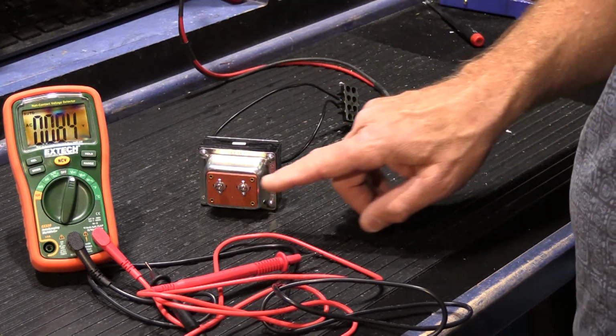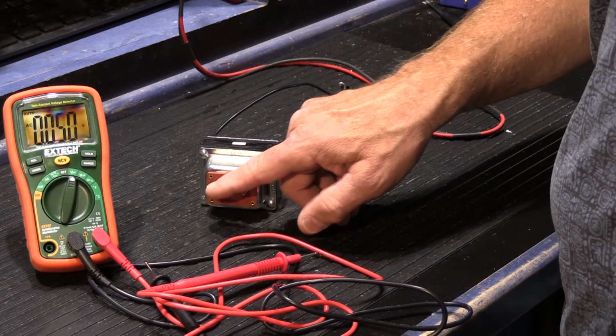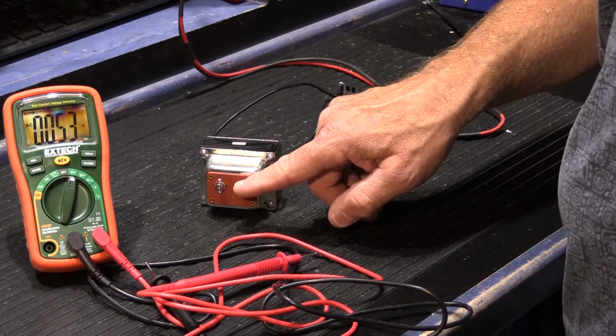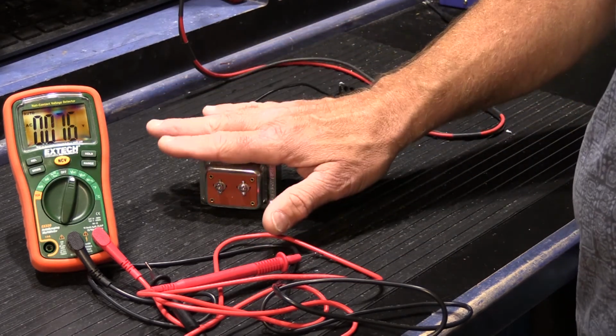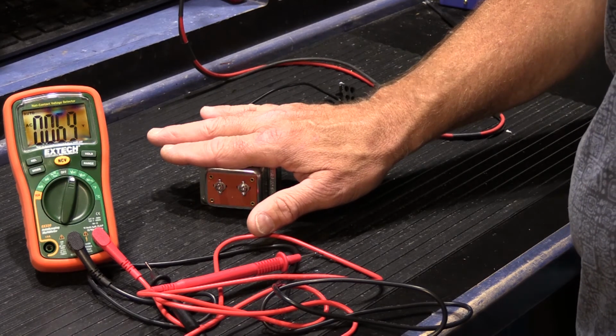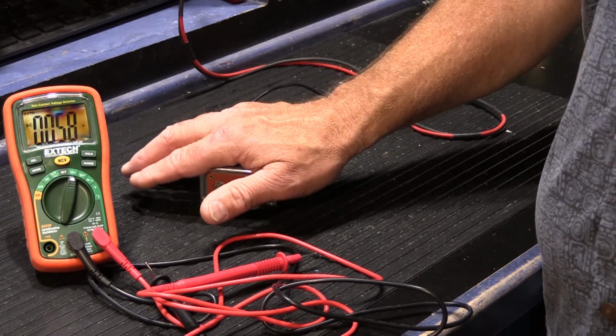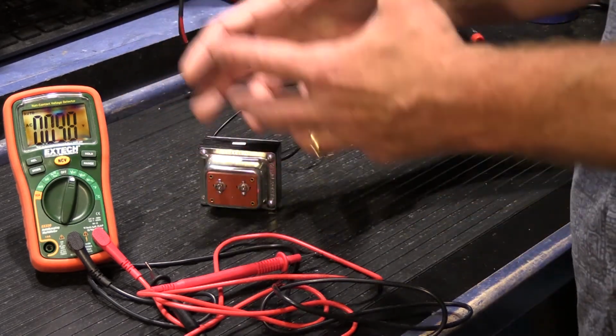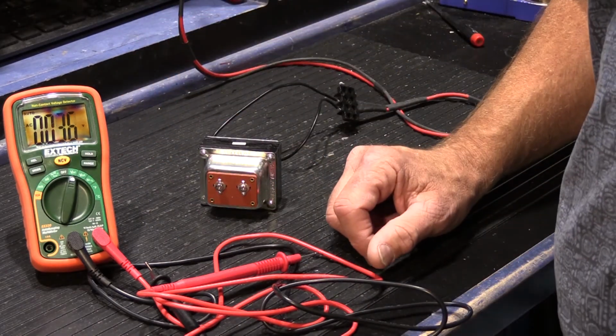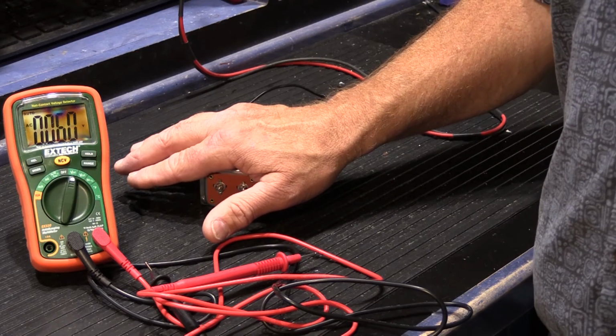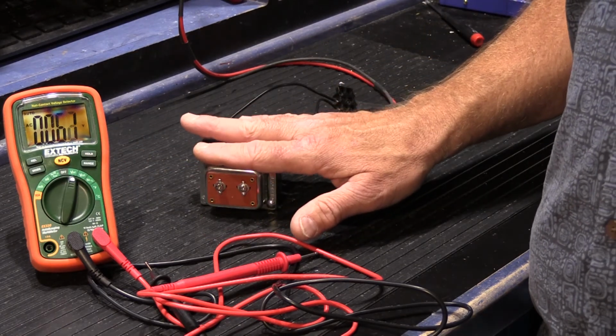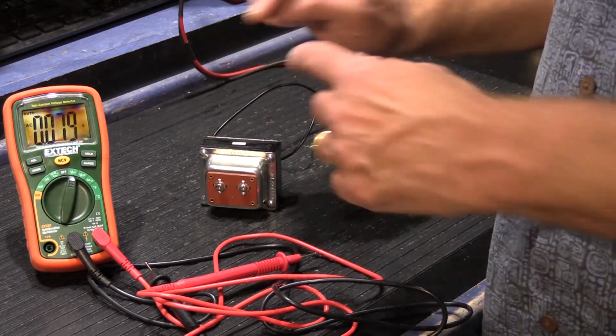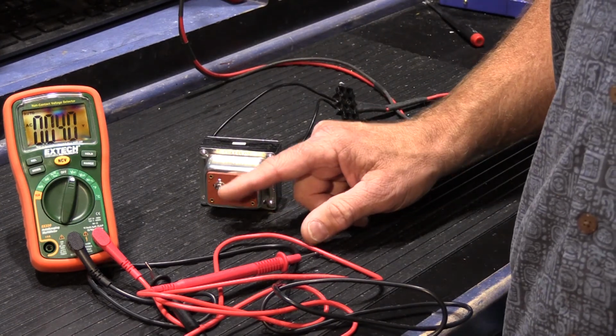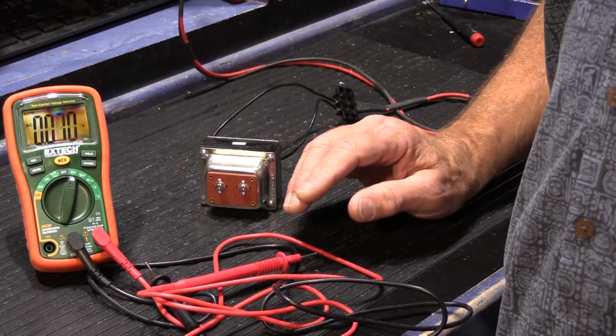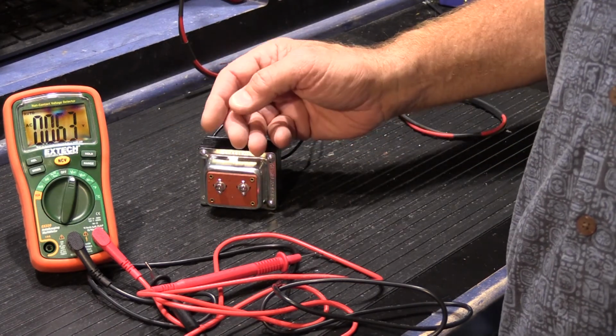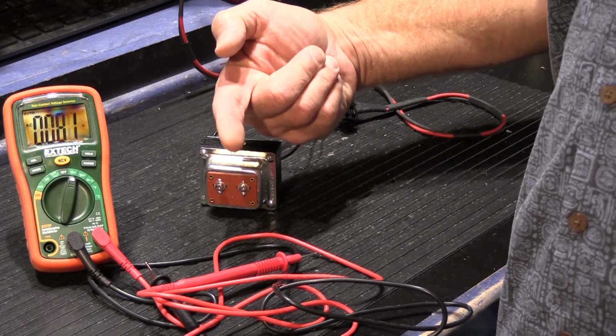You take the wires off the secondary side of the transformer that connect it to the intercom system. Give it about an hour or so to cool down, with the intercom opened up so air can flow around it. Once it's cooled down to that very slightly warm to the touch condition, measure it again. You'll probably find the voltage has come back up, the transformer is cooled down and happy again, and you'll know the problem is over there with the intercom system.